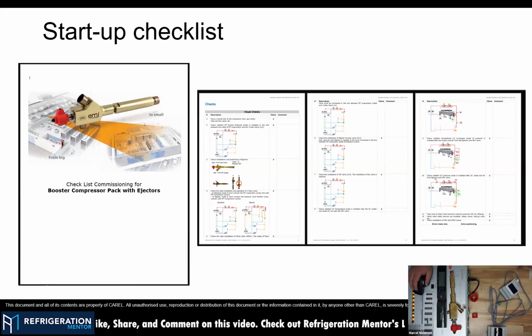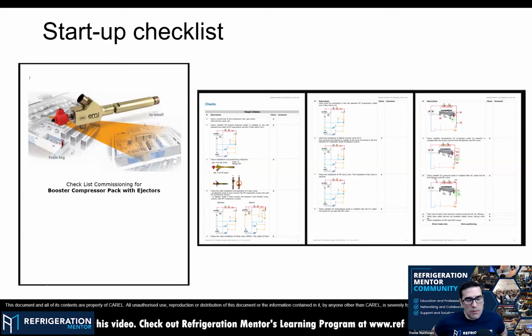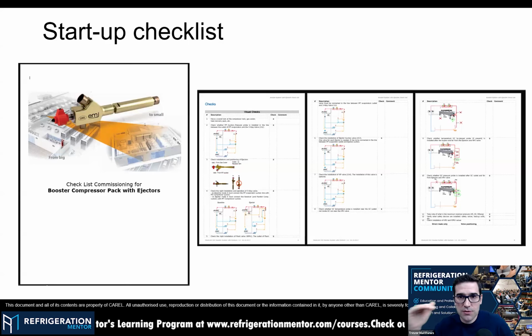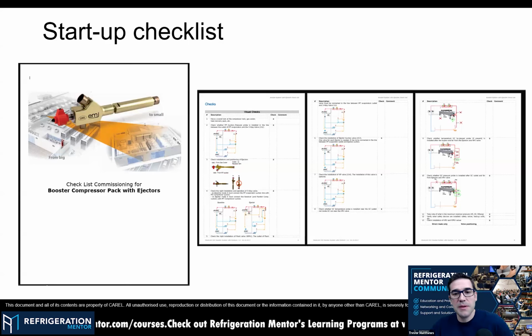Okay, so it's a good document that we can share and can support the technicians in the field during commissionings. And what's great about that is you just go through it step by step. It's like any compressor checklist, the checklist that we do in our CO2 training programs. You go through that when you're doing a startup, because I've been to lots of startups. You go through the checklist and check everything off. Did I check this? Did I check that? That's what it's called, a checklist. And when you go through that and say, okay, I verified this, I verified that, then you run into way fewer issues than if you say, oh, I think I did it, or yeah, maybe it's good. You know what I mean? So always do those checklists. Be diligent.